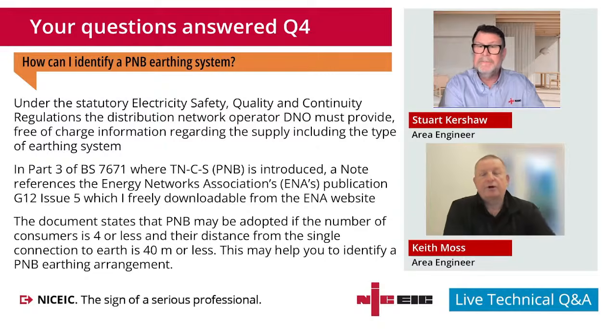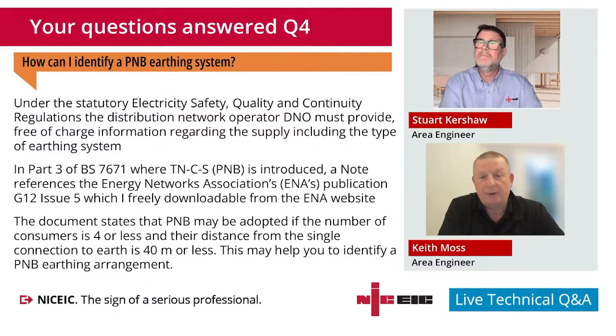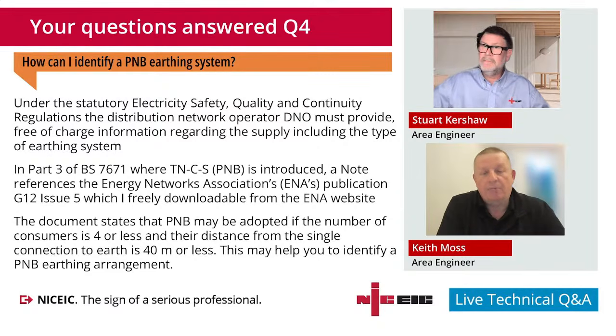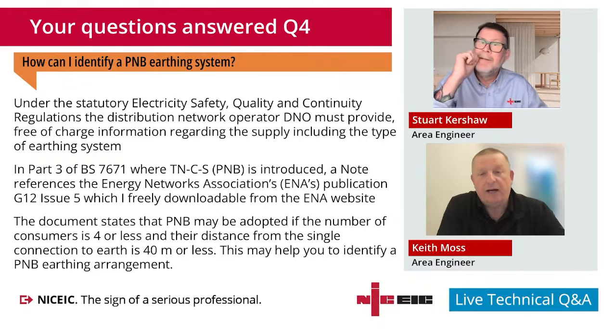Sam, I think the extra earth rod as well is really a consideration if you're going to go into island mode more than anything else, isn't it? So normally you think maybe that would only be new builds, so you might have the facility to put an extra earth rod in, to supplement the other system, if you're going to use the disconnection relay for going into island mode.